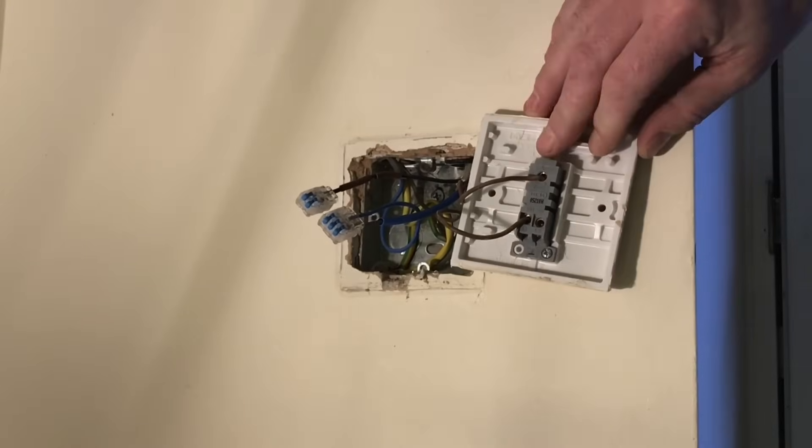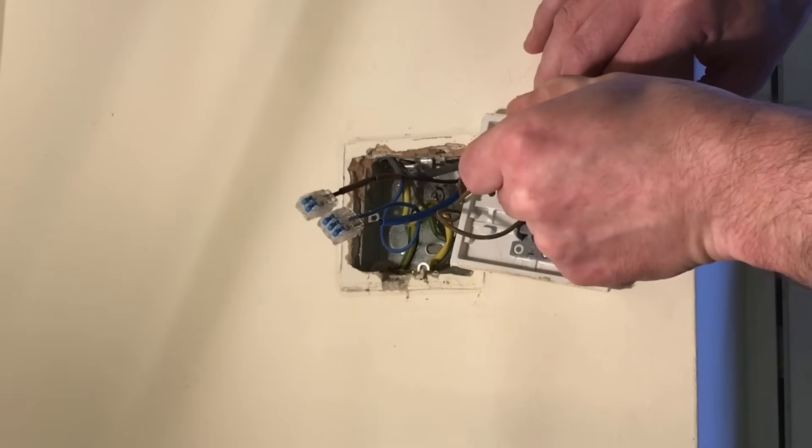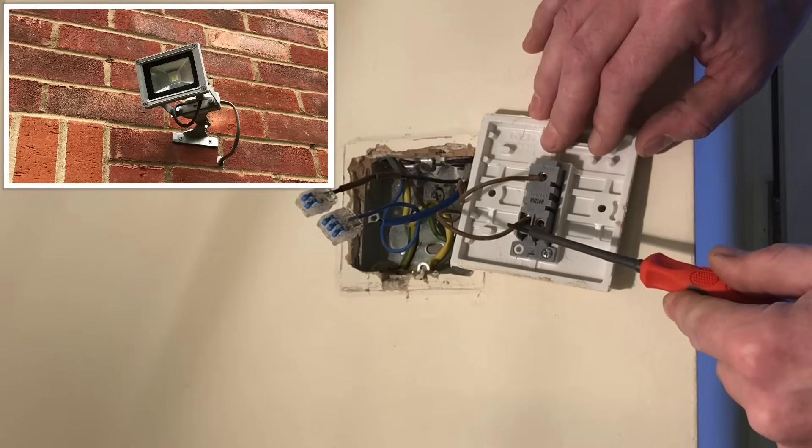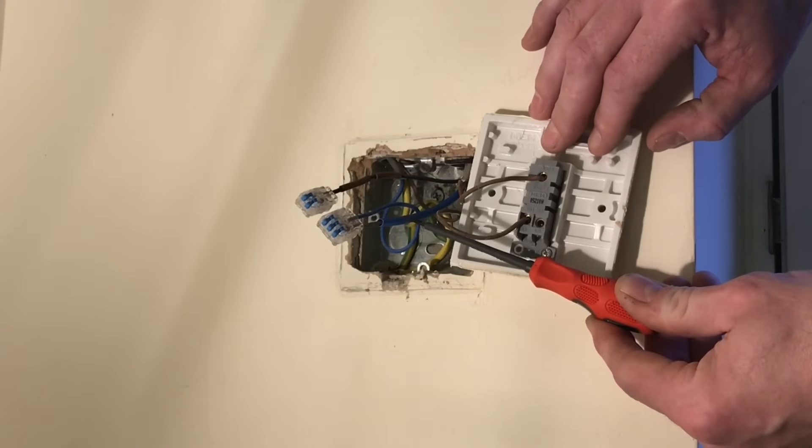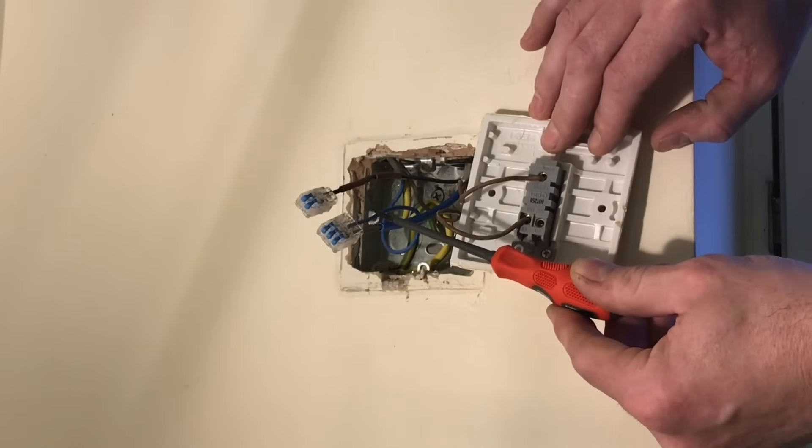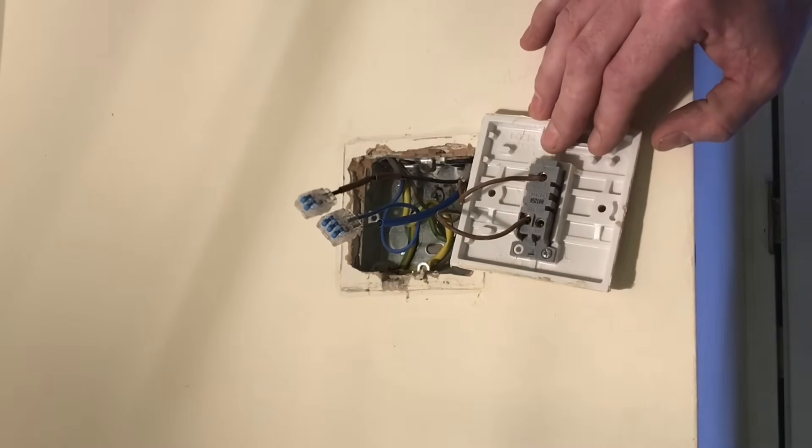So what we've got then is the top connection here in the common is the brown of the 3 core bringing in our feed. We have a twin and CPC going out to an outside light, so this is the switching line conductor. Previously saw that grey was used with blue sleeving for the neutral, so that brings our neutral in. Goes out on the blue neutral to the outside light, and once again the black conductor, which would have been a switching line on a 3 core, is actually redundant and doing nothing.